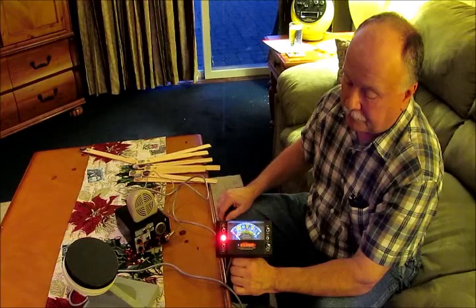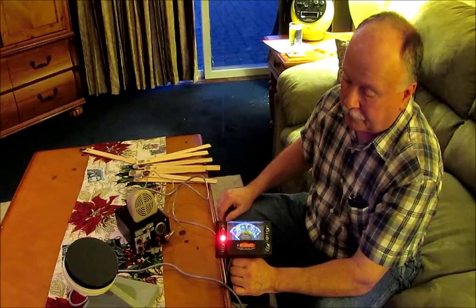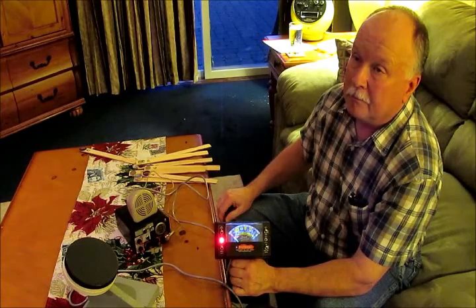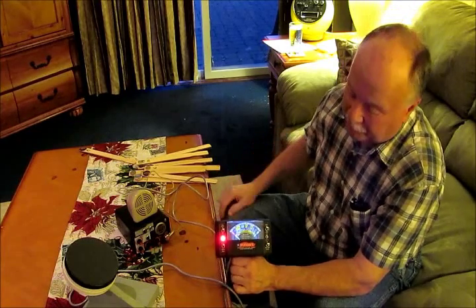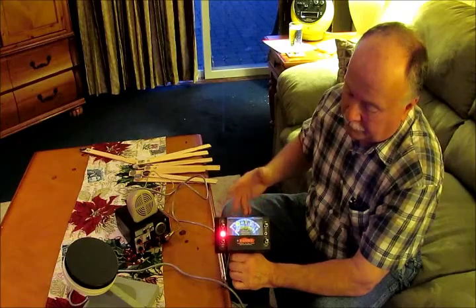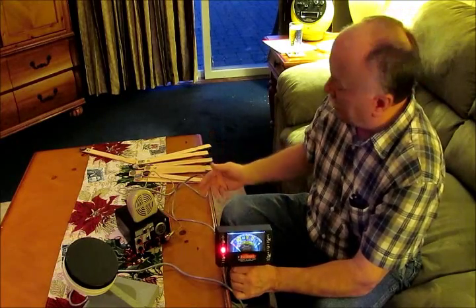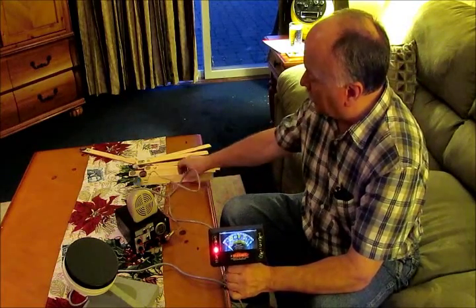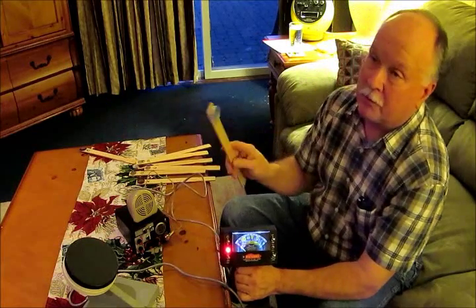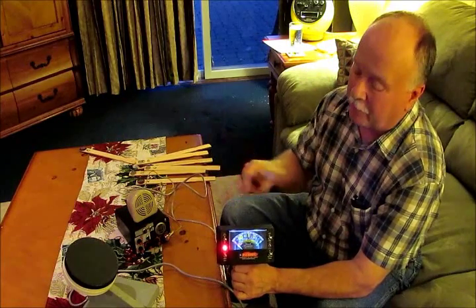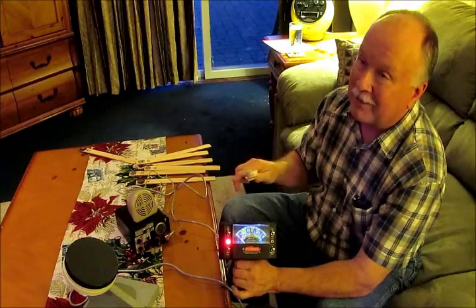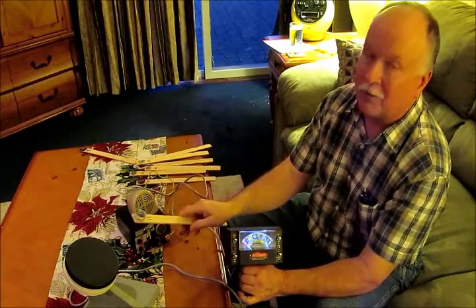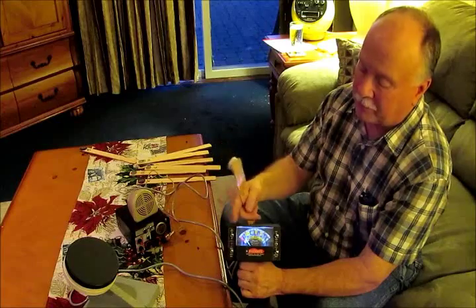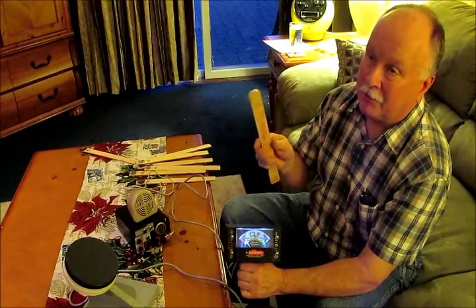That's in fact part of not only the calibration of the actual target, but the fact that the machine is accurate right with the meter. And I was showing Bill before, for example, you wouldn't want to do this, but let's say instead of using a quarter to calibrate it, you used a screw cap, just to show you that it's not a gimmick. It does in fact look at the target, and it does calibrate the meter to 180 on the target.